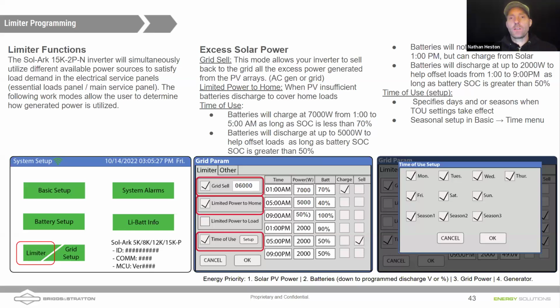Limited power to home, what is that, Daniel? That's so that we keep everything limited to the home and we're not going to be backfeeding. Yep. And then limited power to load. This is more common with the 8K and the 12K, when you don't have all of your load connected through the inverter. You could limit power to the home, you could limit power to the load. What that does is it uses the CTs to measure how much power is being pulled from the grid, and it exports the difference between the amount of power pulled from the grid and the amount of power it's sending to the loads panel. And it'll backfeed that to your load center, but not necessarily send any back to the grid. So you can use that limited power to home for that.